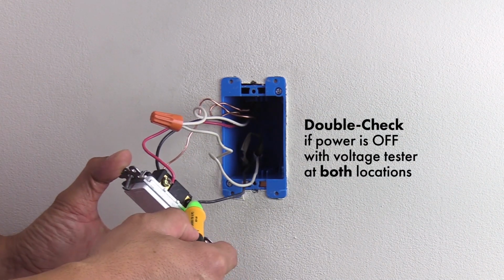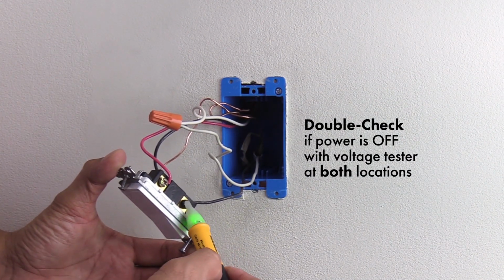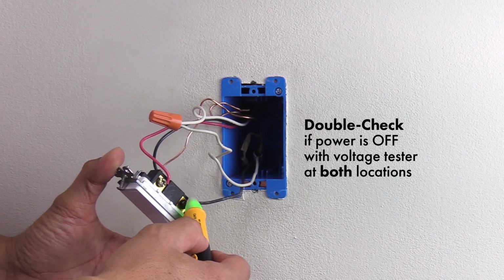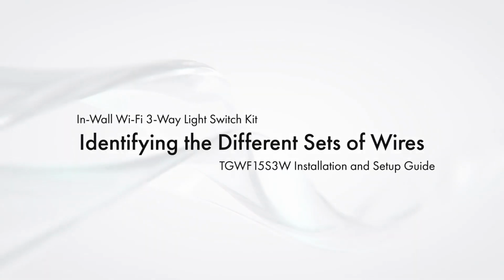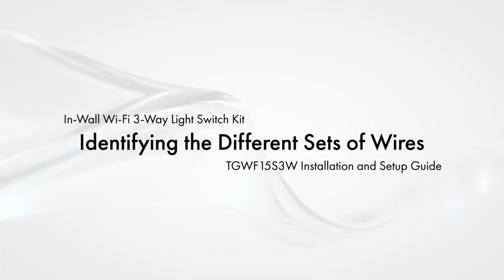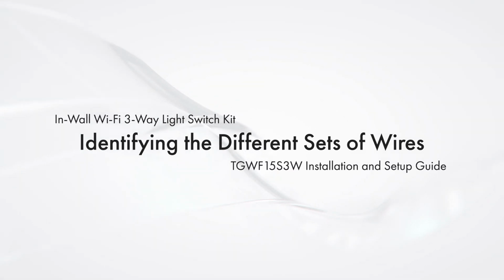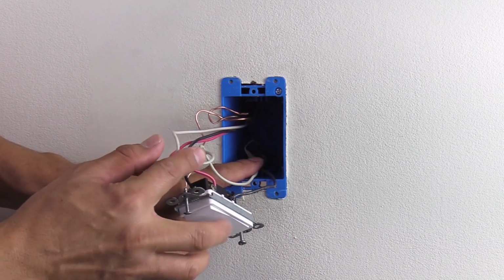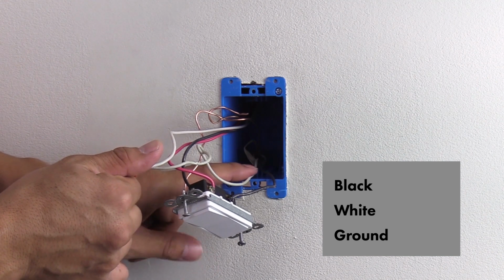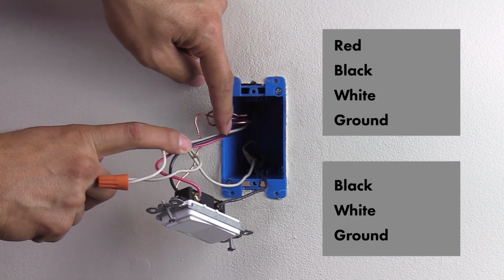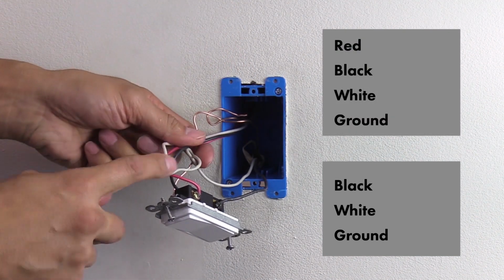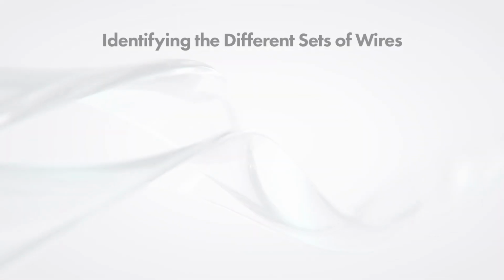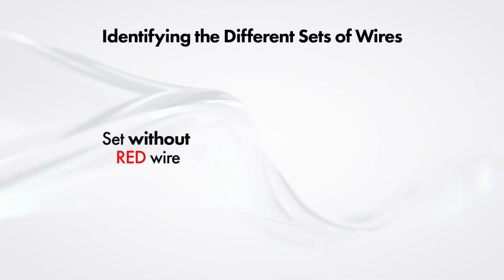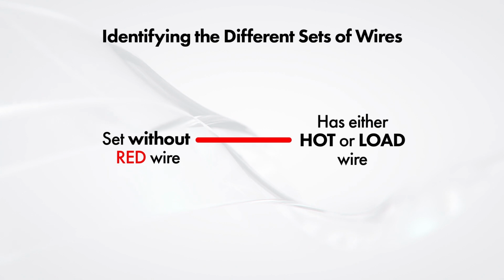Double check if the power is off with a non-contact voltage tester at both locations. You should see in the switch boxes that there are two sets of wires that enter the back of the box. One set should have a black, white, and ground wire. The second set should have red, black, white, and ground wires. The set of wires that does not have the red wire will either have the hot or load wire. We will determine this in the next steps.